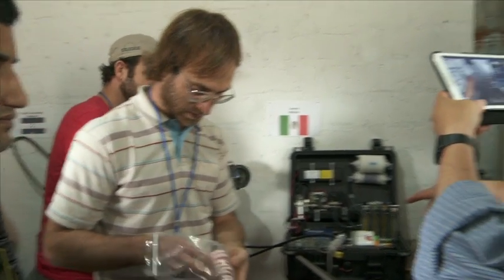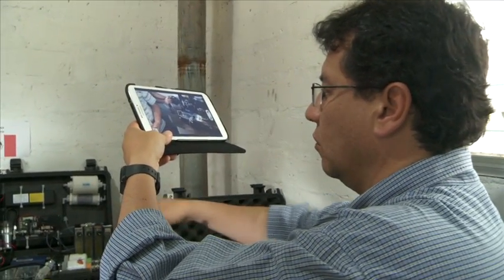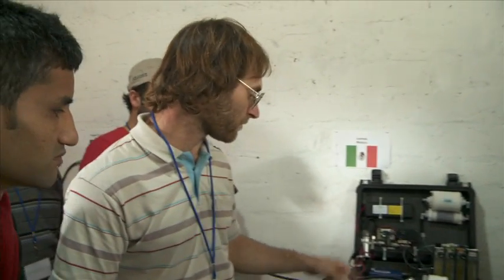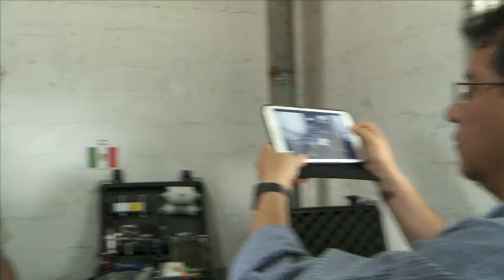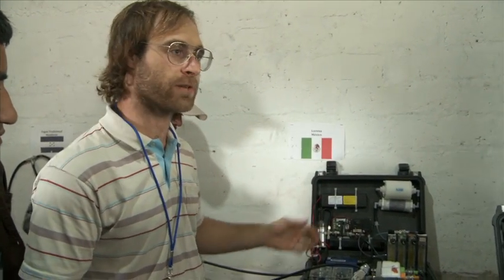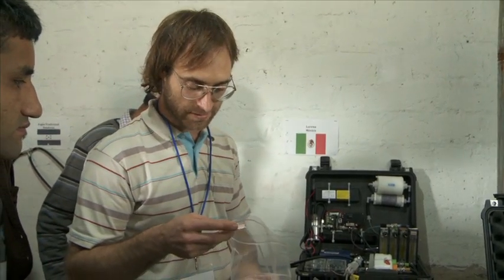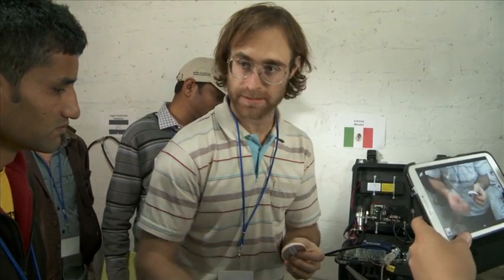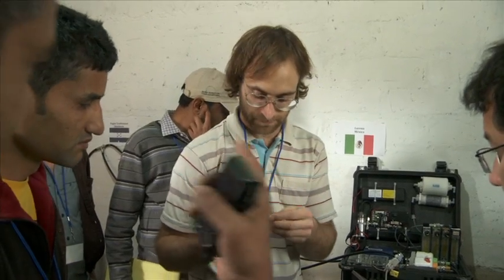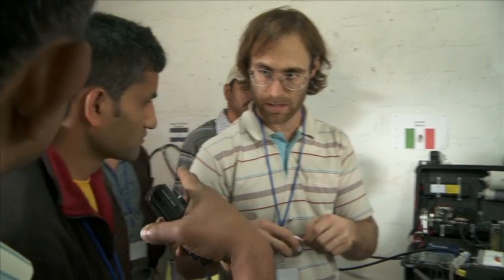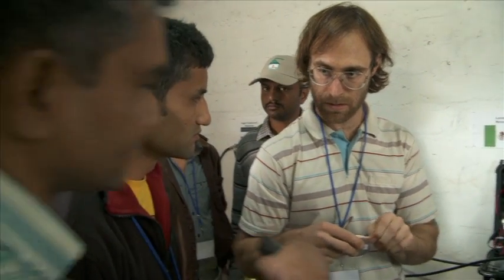Why do you need 2 sensors for CO2 and CO? Well, one's for the sample and one's for the background. If we're putting in air from the room that has some carbon monoxide in it, we need to know that in order to correct our calculations. So are you measuring the concentration or ratio on a wet basis or dry basis? The dry basis. It's all done on a dry basis. So dilution here is dry, but the stack emission that comes from the chimney.